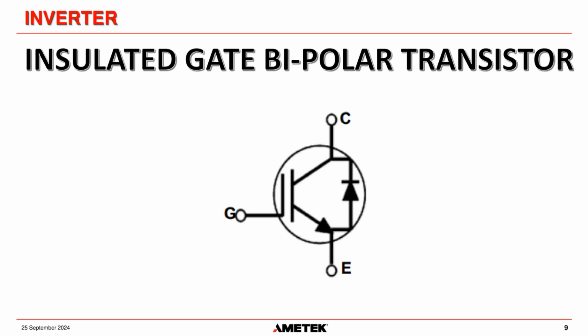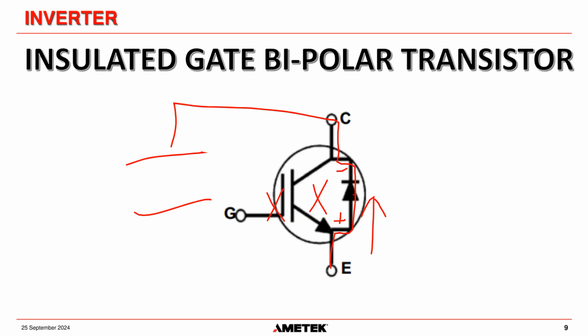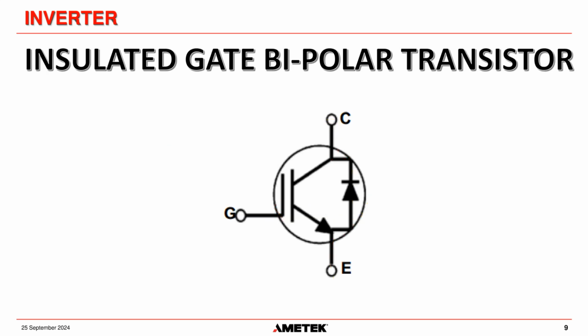But if we have a situation where there is inductance in the load, if you turn off an IGBT, there can be a back EMF generated because you're interrupting current flowing through an inductive circuit. When that happens, a back EMF is caused, and you will have positive and negative there. What this diode allows is, rather than damage the IGBT, current to flow through that diode. We usually have a capacitor bank back here in the inverter bridge, and it allows that inductive kick to flow through that diode and back to the capacitor or the battery, whatever the DC circuit is.